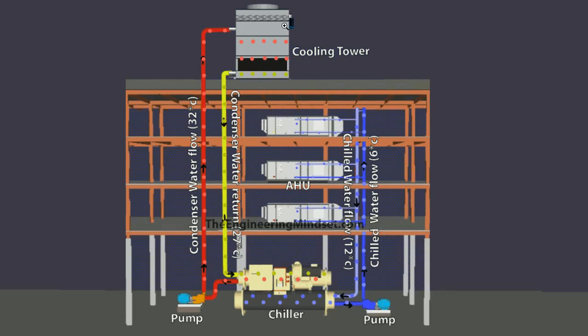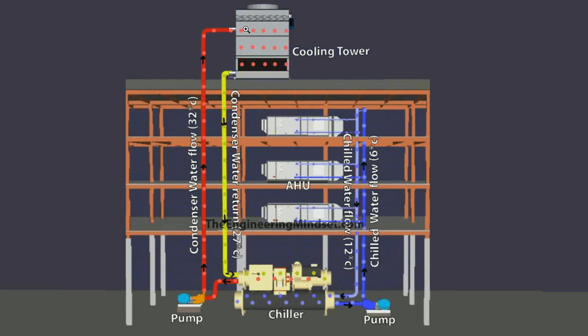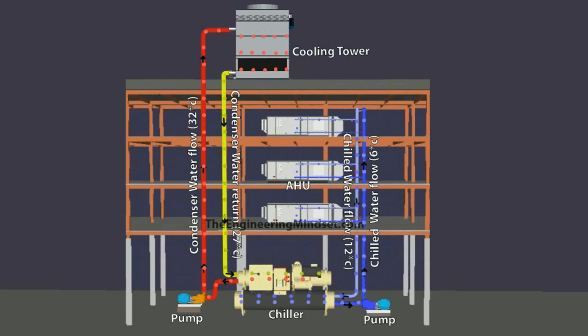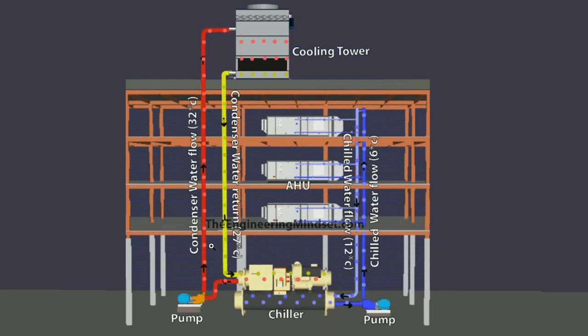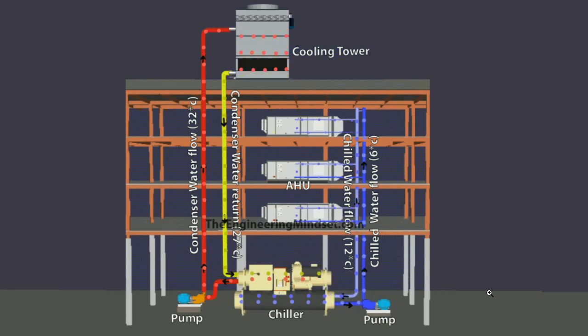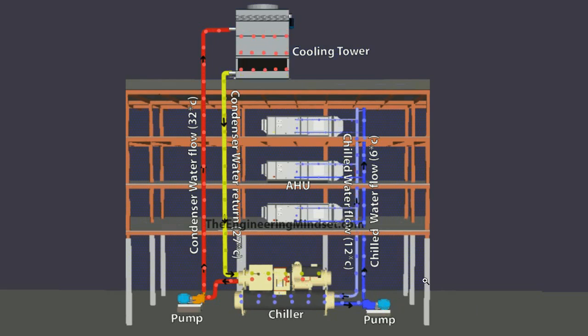It could also be that the water distribution within the cooling tower has become disturbed — there could be a lot of leaves or debris inside stopping the water from flowing and creating the large surface area needed to disperse thermal energy, so the cooling tower doesn't reject the required heat. Additionally, the pump strainer might become blocked, reducing water flow. The distribution tray at the top may become blocked with scale and debris, and the tubes inside the condenser may become covered in scale, reducing heat transfer surface area — this is known as fouling.